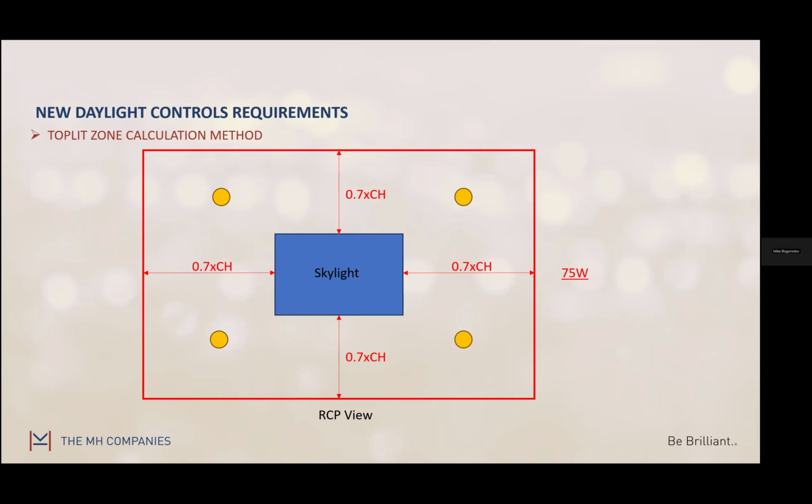Regarding the theater questions, if there's a gym specifically that doubles as a fellowship hall, yeah, I believe that's kind of what I imagine this might be. Addressing the actual theatrical lighting itself, what I'm imagining is there are some projectors that shine on the stage, or track lights that would light up a stage. Those for sure do not have to be daylight harvested. However, your house lights may need to be daylight harvested.